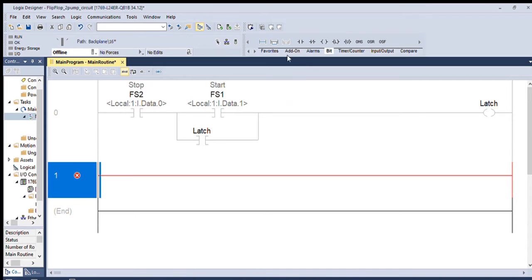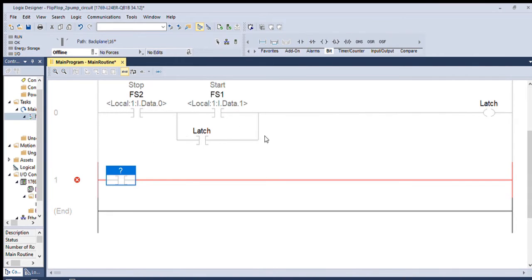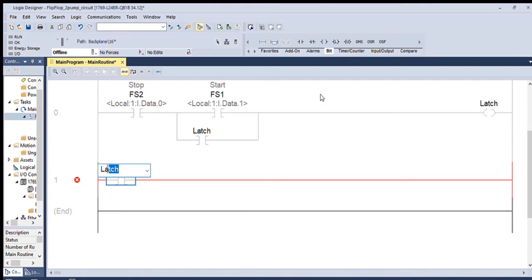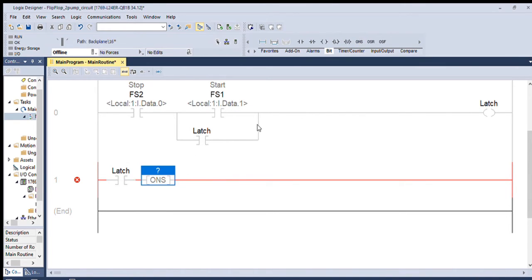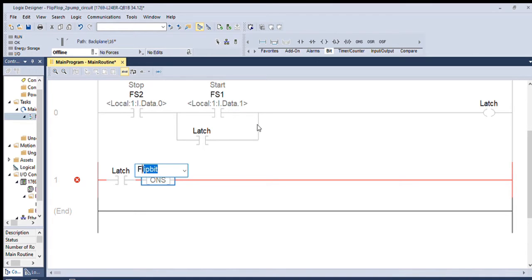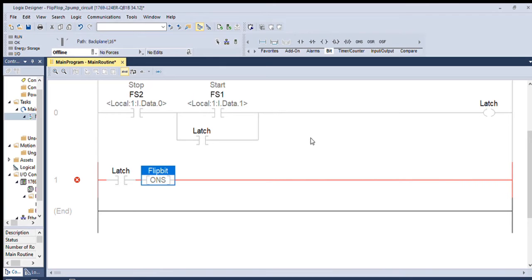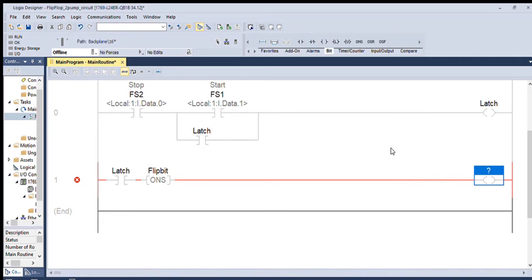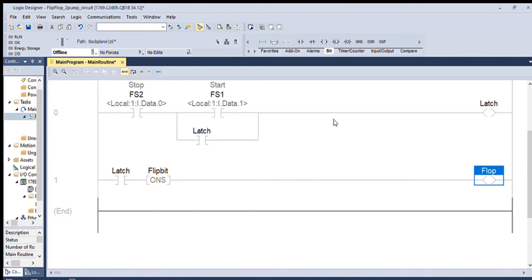Now I'm going to go and take my latch again. It's the thing as I start and stop the system. It's going to make all the magic happen. Now my latch is going to go and trigger an ONS or one shot. And this is the thing where it only happens once during a scan cycle. It'll send out a signal and that's where the goodness happens. And I will call that a flip bit. So that is the bit that's going to help us do the flipping. And what is it flipping? Well, I'm going to ironically enough have it flip the flop.